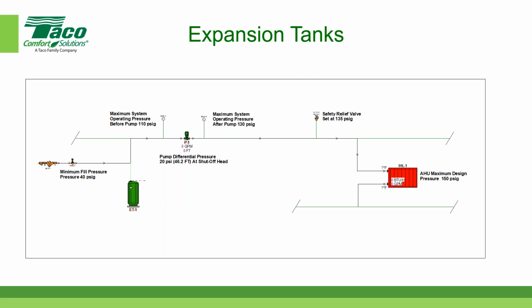And not that you can do this at home, but Mike says, good luck finding a 135 PSI relief valve. You know, that's the second time I've gotten that comment, but yeah, that's a good one. That's why we're showing concepts here. This is one method right here. One method. Okay, so now we've established the minimum pressure, 40 pounds, and the maximum at the expansion tank.